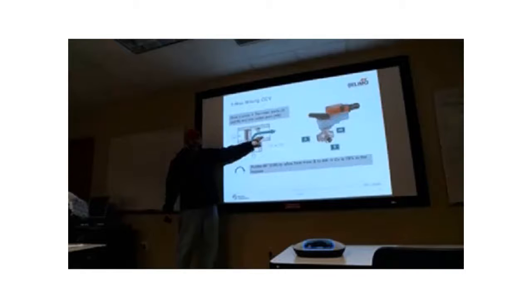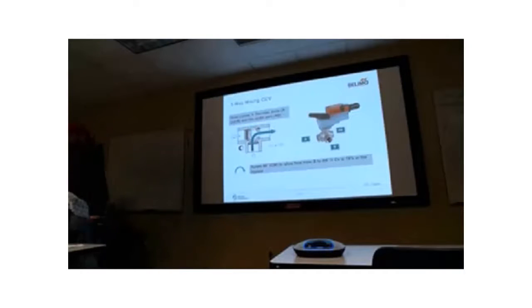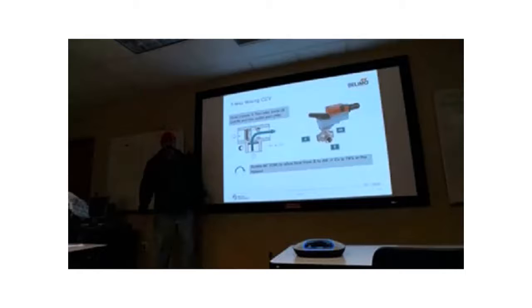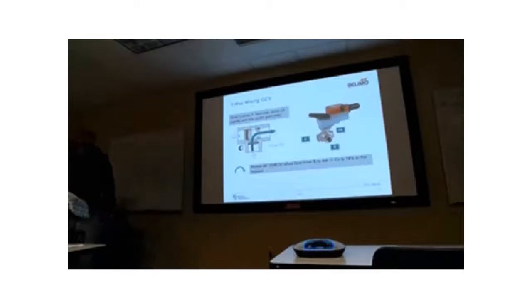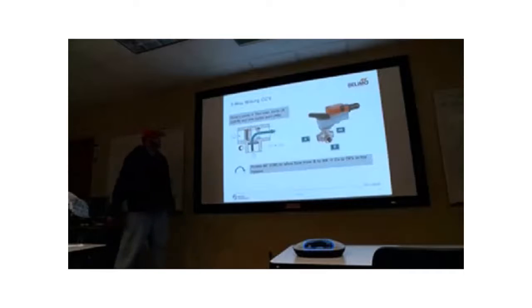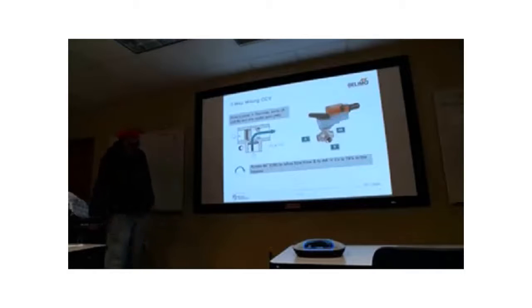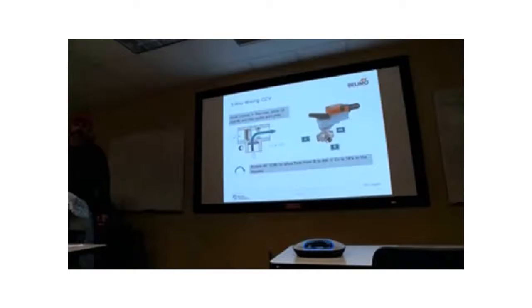We had a situation locally here probably about 7 years ago where we had a mechanical contractor put some snow melt in like one of the local schools, or it was like a sidewalk system. They put the valve in wrong, and so what happened when it froze? It froze the coils right in the slab. They were pissed, and they told us that, well, wait a minute, Belimo said I could do this, and I said no, I don't think Belimo said he could do this because we're really well aware of this. Anyway, it was a bad scene. But here's what I'm trying to beat to death a little bit: be careful with these 3-way valves and make sure that that actuator goes back on the same way that it came off.